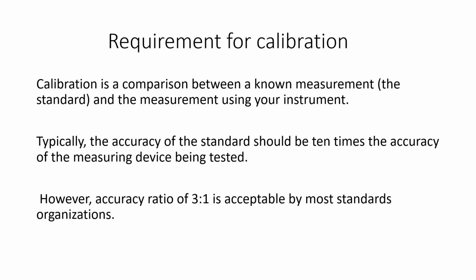Now, if it is not the case that it is 10 times, then the minimum requirement is that the accuracy ratio should be 3:1. This is acceptable to most of the standard organizations, but below this, no, it is not acceptable.